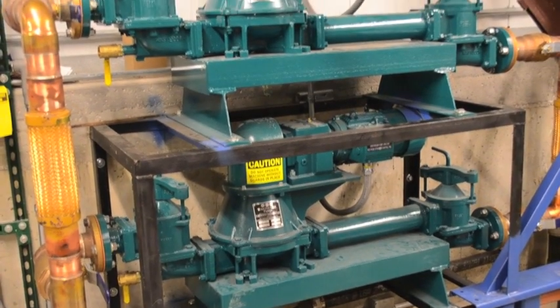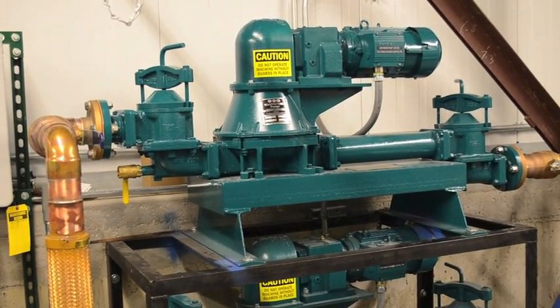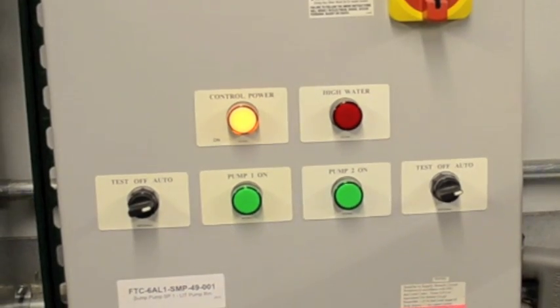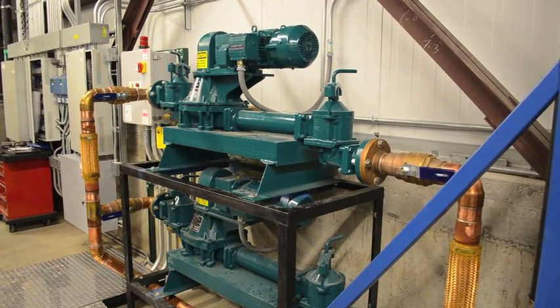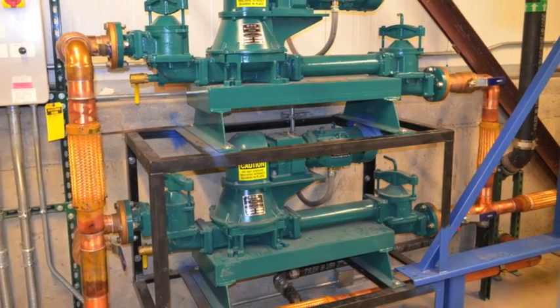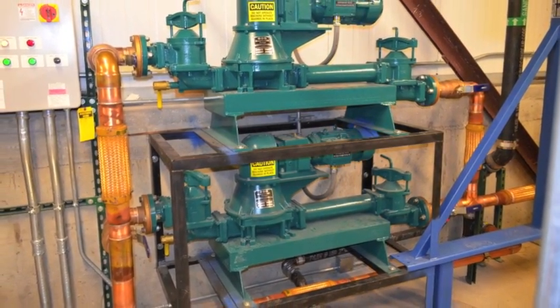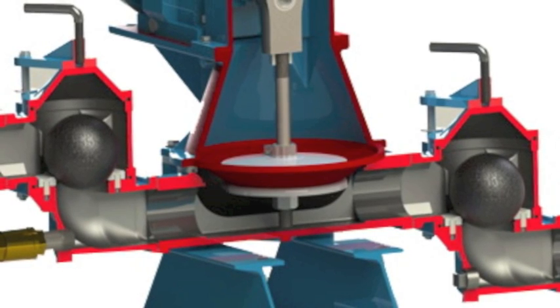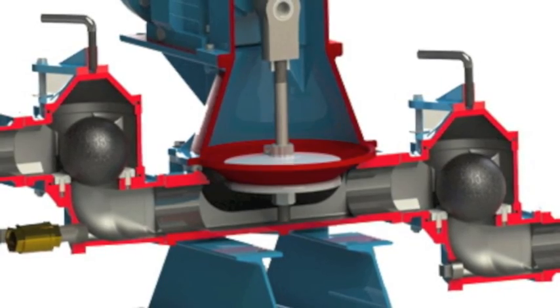In keeping with the client's goals for reducing the environmental impact of next generation data centers, WasteCorp designed the Mudsuckers with energy saving Siemens three-phase motors and SEW EuroDrive gearboxes. The client's Mudsuckers were designed with an in-line piping configuration to save space at the facility. Santoprene diaphragms were also included to help maximize component life with higher temperature liquids being constant.